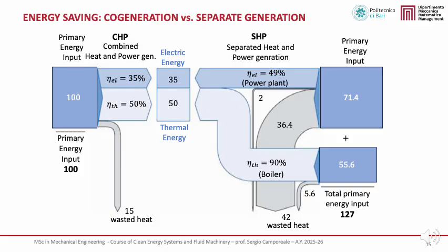Now let us consider the case of separate production, shown on the right side. To generate the same amount of electricity, a conventional power plant with an electrical efficiency of 49% requires about 71 units of primary energy. This result can be obtained dividing 35 by 0.49. To produce the same thermal energy, a boiler with an efficiency of 90% requires an additional 56 units of primary energy. Result that can be obtained dividing 50 by 0.9.